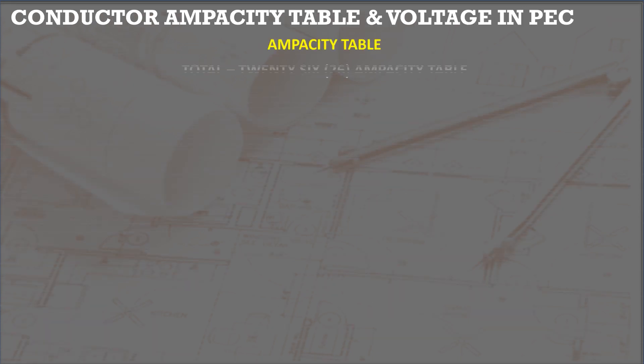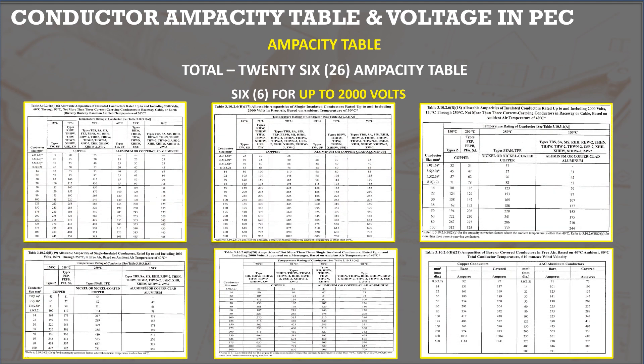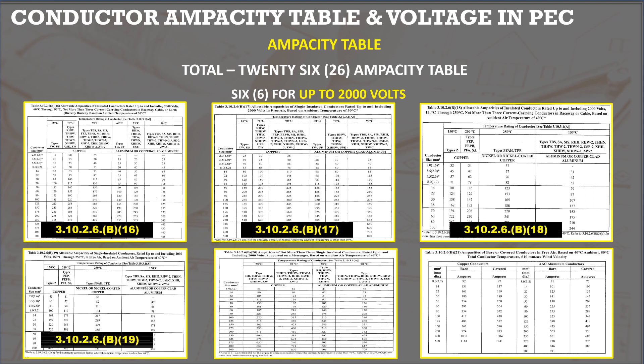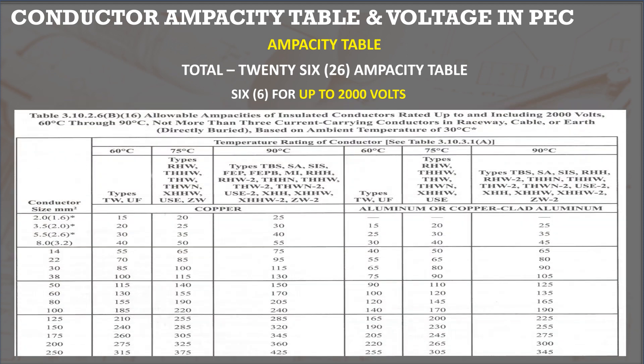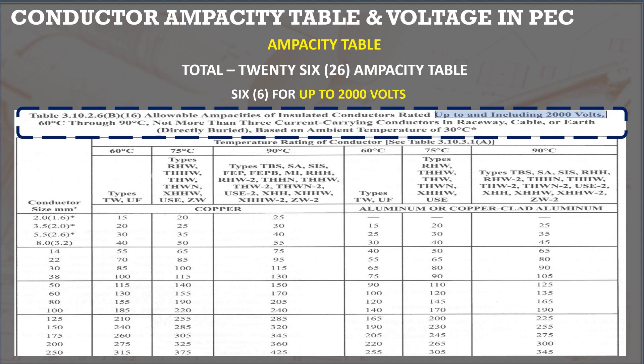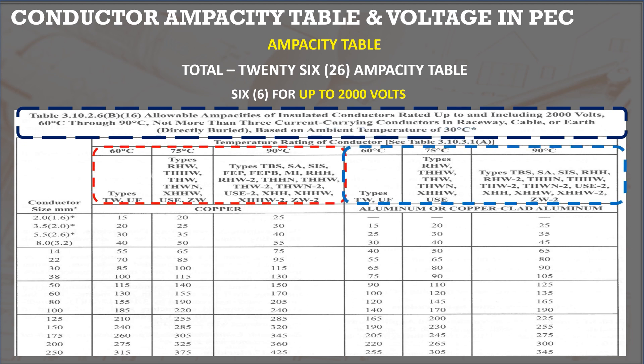There are more than 20 ampacity tables in the PEC. Six of them are for 0 to 2,000 volts, all in Table 3.10.2.6 B16 to B21. The top part of each table shows the method of installation or application, the voltage rating of 0 to 2,000 volts, insulation temperature rating, number of conductors in raceways, and installation method. The table is for an ambient temperature of 30 degrees Celsius. There are two types of conductors — copper and aluminum — and columns show ampacity depending on insulation type and material.